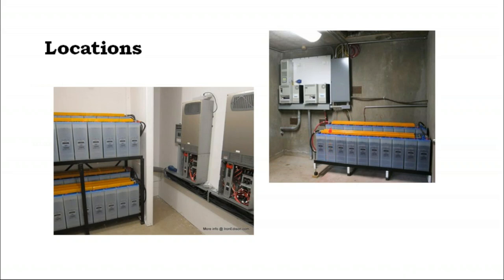There's a 6-inch depth clearance requirement. An electronic box can overhang another electronic box, but by no more than 6 inches, to prevent you from having to kind of lean over and stumble into live electronics. There's also a space requirement of clearance between a wall and the electronics as well that this is probably in violation of.